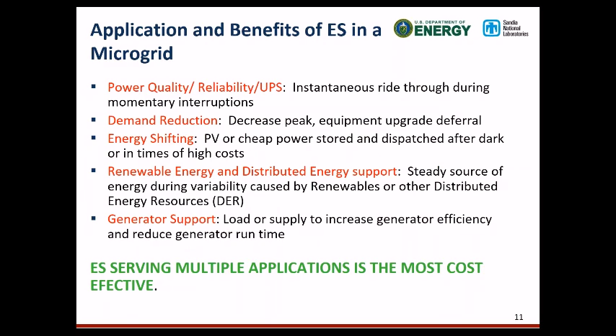If we have time, I'll show a couple case studies where we actually used energy storage to decrease the peak for a utility. They were therefore able to reduce their capacity payments to the ISO. You could also use it for energy shifting — this is mostly used in PV, but it could be used for other things as well. And then you have generator support, where if you're running a generator, such as in Alaska or somewhere in a remote area, some island or microgrid type application, the energy storage could be utilized to reduce your runtime on the generator, therefore reducing cost in fuel and maintenance.